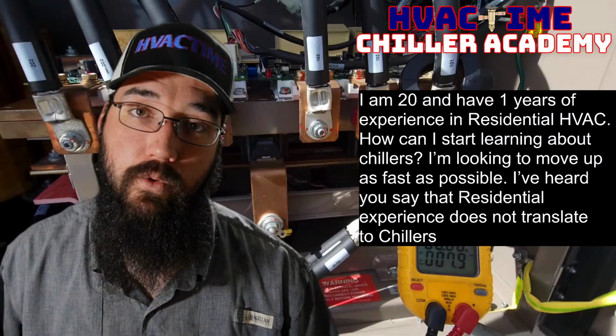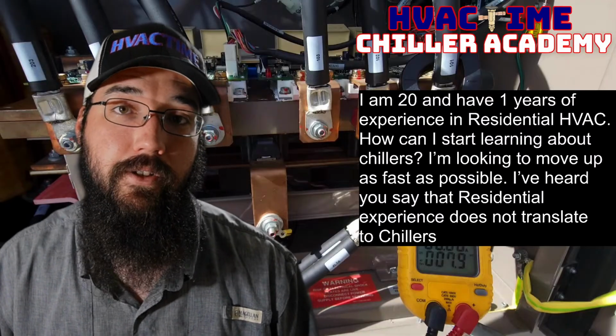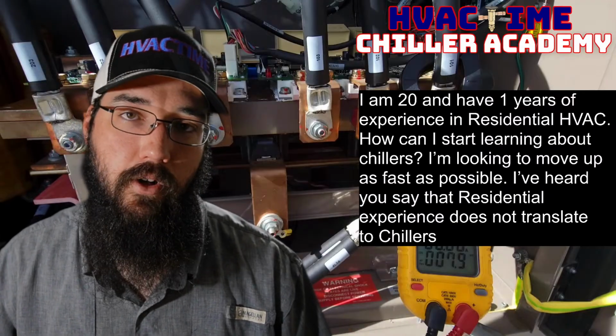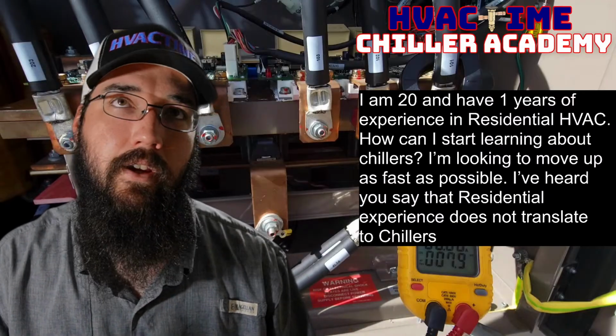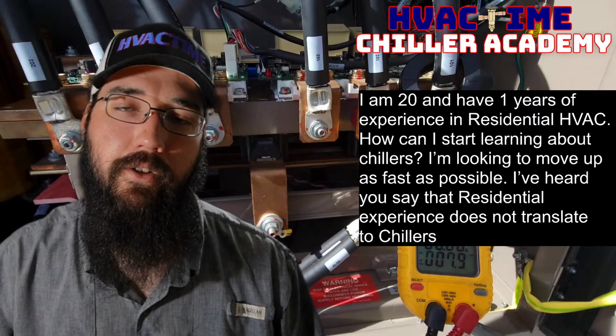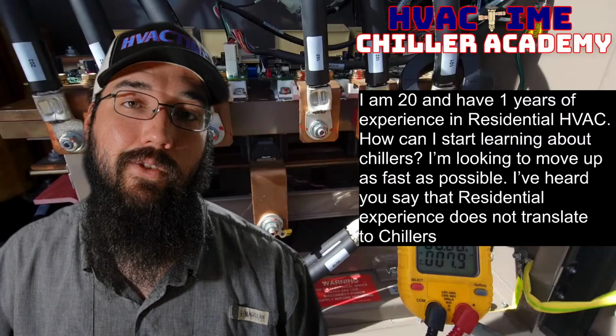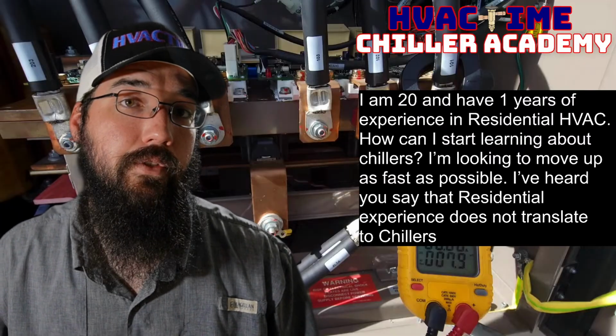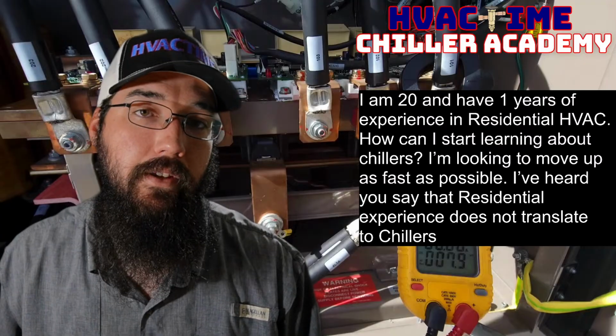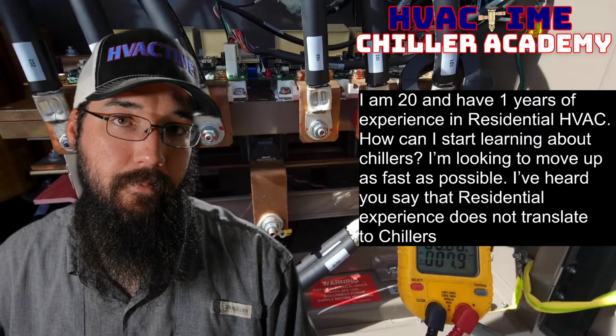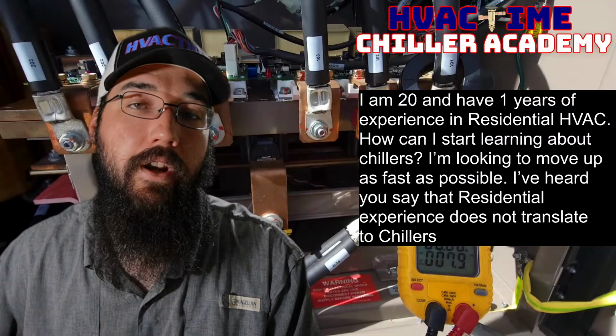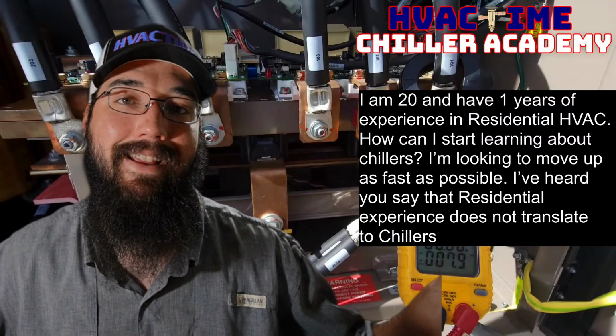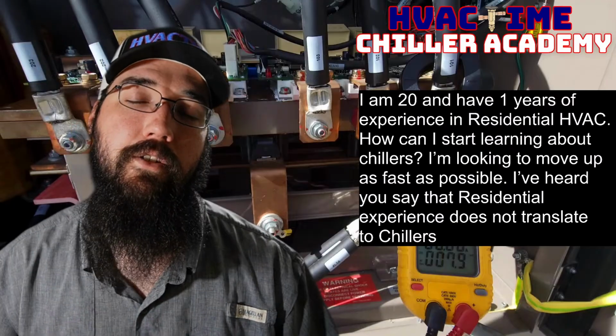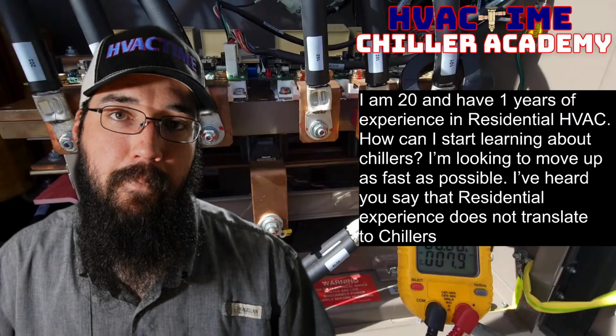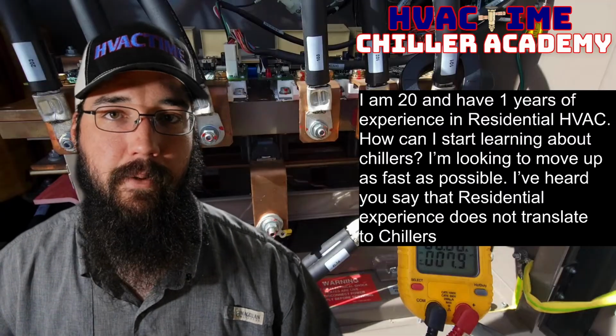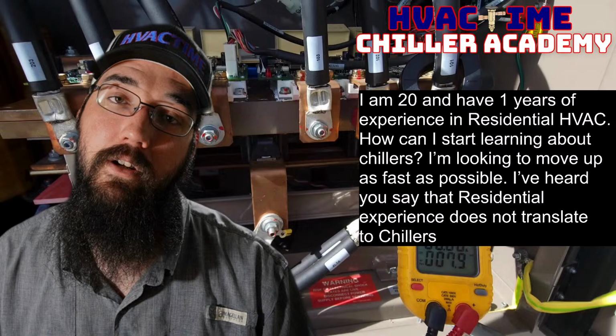There's also lots of tools that correlate. We use the same service wrenches. Now, albeit there are larger ones, right? So you've got the 3/8, 5/16, quarter standard service wrench, and we get into 1/2 inch and 3/4 service valves. Those would be some things that we just scale bigger because our machines are running at larger tonnages. We're trying to maintain an entire facility where you may be just trying to maintain a single house. And it's just a scale aspect at that point. So the tools scale up larger, but a lot of the same basic tools.